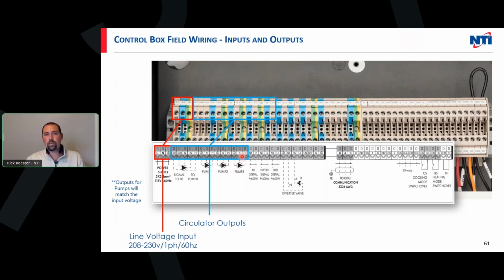Pump 3 is a dedicated recirc pump. So if we are using an indirect or some kind of water tank that has a domestic recirc pump on it, we can utilize this terminal to power that pump, and we can control it through our programs. It's basically a 7-day programmable. You can set the times, the hours, how long it comes on, how long it shuts off for. So all of that is built into the control, which is really cool. I have not seen that involved in anybody's controls, so that was pretty exciting to see. I think domestic recirc is definitely something people are paying more attention to as far as water saving, stuff like that. So it does give us an advantage there.